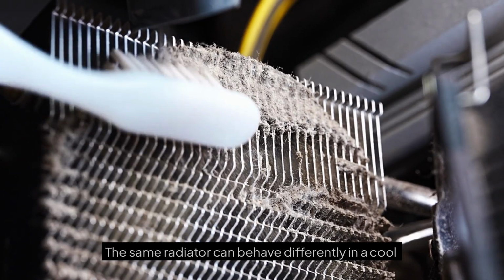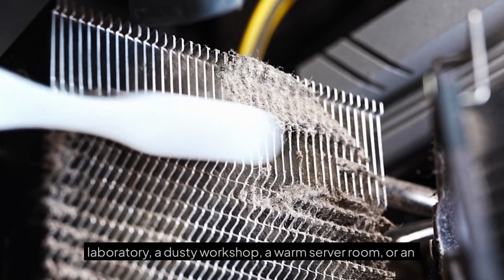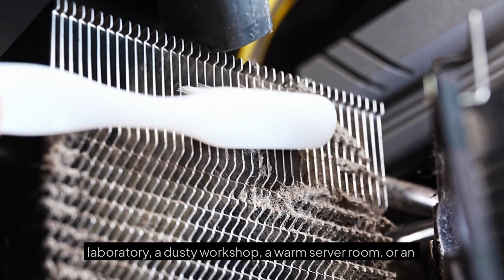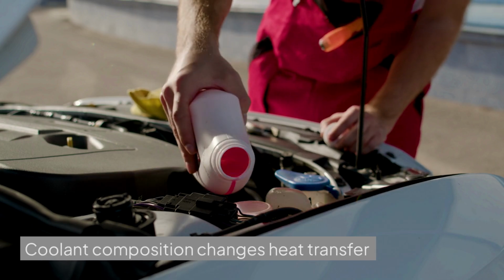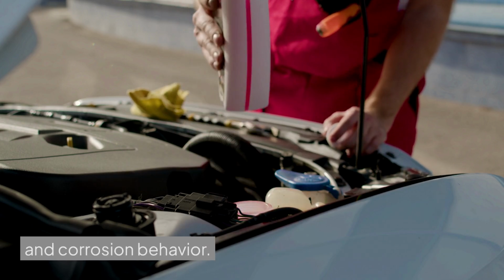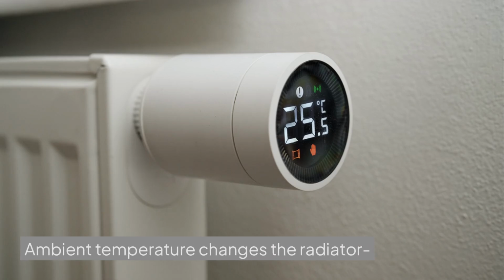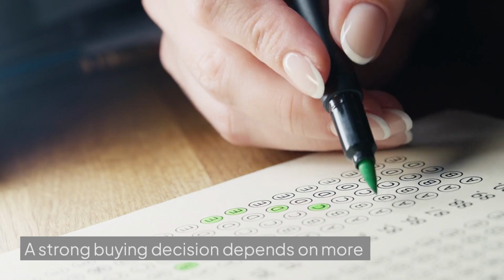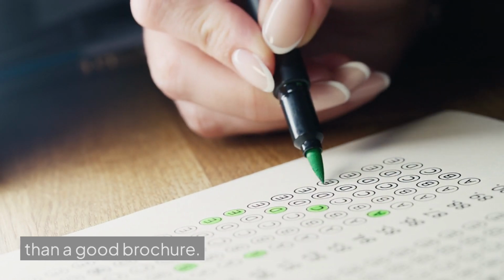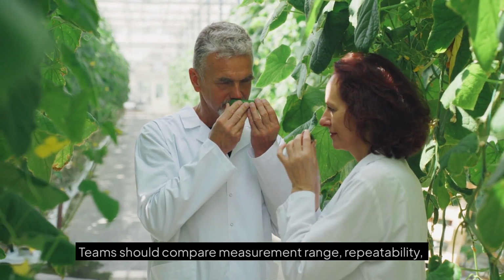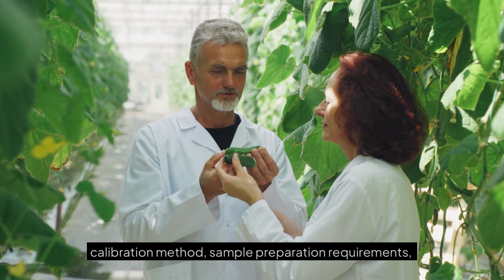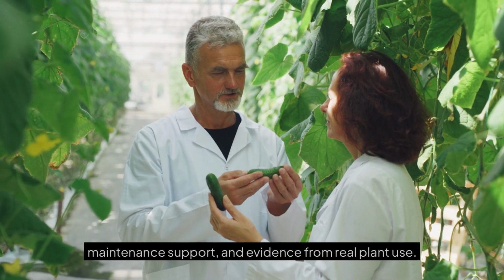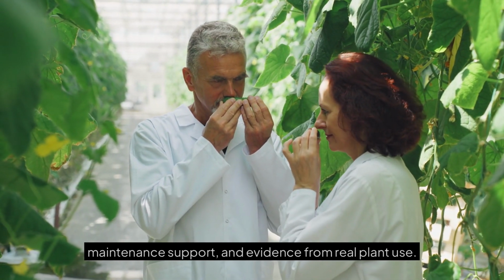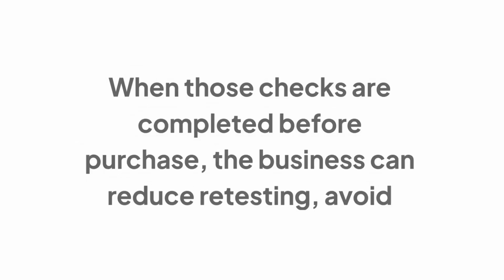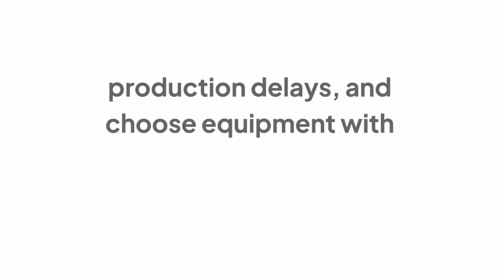The same radiator can behave differently in a cool laboratory, a dusty workshop, a warm server room, or an industrial cabinet. Coolant composition changes heat transfer and corrosion behavior. Ambient temperature changes the radiator-to-air temperature difference. A strong buying decision depends on more than a good brochure. Teams should compare measurement range, repeatability, calibration method, sample preparation requirements, maintenance support, and evidence from real plant use. When those checks are completed before purchase, the business can reduce retesting, avoid production delays, and choose equipment with more confidence.